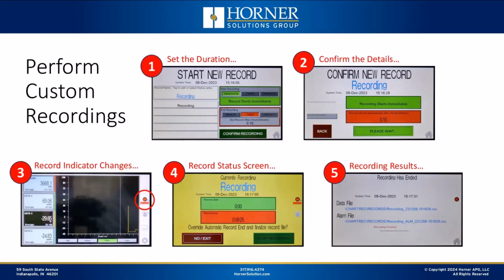Now, one of the extra capabilities this unit does have, which is quite handy, is this custom recording function. So again, if you're maybe in a test bench type scenario or in another application where you're going to be running periodic tests of a limited duration, then it's very handy that this product supports that. So the process is effectively a 5-step process from beginning to end. When you're ready to run a test, a special test, you're going to go in and set that up. What is the duration of the test? What triggers the start of the test? Once you've got that configured, it's going to ask you to confirm the details that you've configured. Once you've done that, the test is going to start.